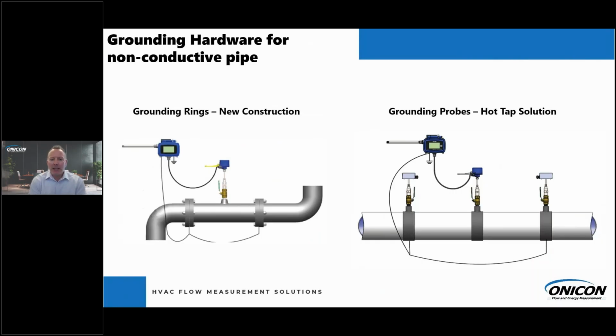Next, a couple of things you have to keep in mind when we're talking about electromagnetic technology is when you're dealing with those non-conductive pipes, anything from PVC, HDPE, Aquatherm that we're seeing quite often now, you have to think about the grounding rings and/or grounding probes that you will need to order for our flow meter to operate correctly and ground the meter. So the flanged is going to be the grounding rings, and then if you do need the probes, say it is in an already existing pipe, you can hot tap the probes as well.